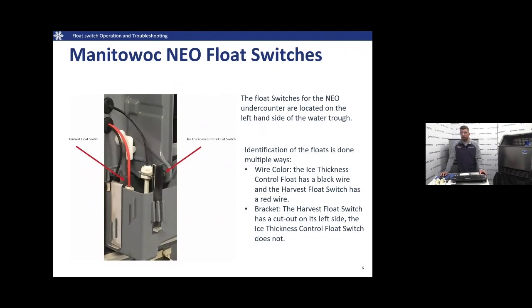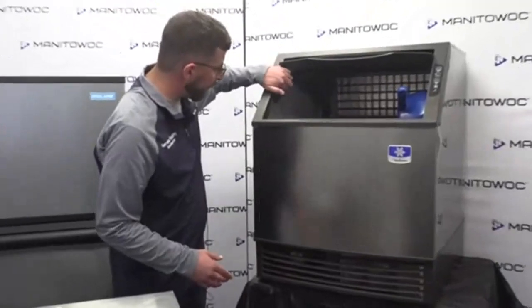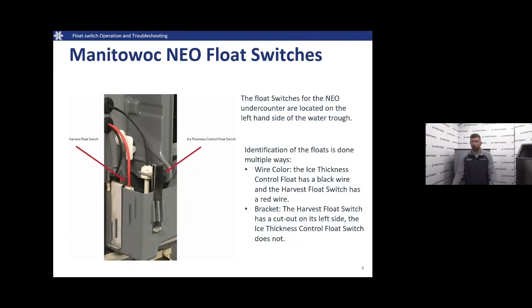The floats on the NEO are located in the water trough, on the left side of that water trough, as shown on screen. There are a couple of ways to identify these. The front float — your ice thickness control float — has a black wire coming out of it, and the bracket does not have a notch on the sides like the harvest float switch. The harvest float switch has a little cutout to lock it in place. It also has a red wire coming off the top going through the bulkhead. Those are the main ways to identify your float switches on the NEO undercounter.